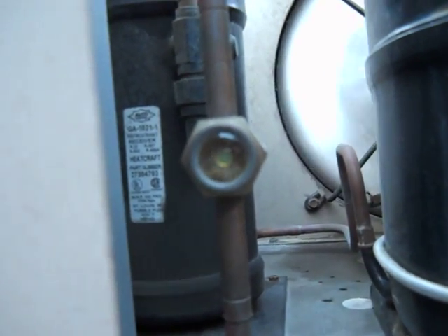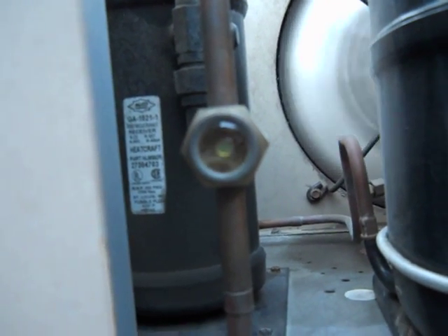This is a sight glass — hopefully it focuses decent — that is low on refrigerant. The liquid is actually coming in from the top, and the liquid is what you see at the bottom, just the liquid. And that's an air space.